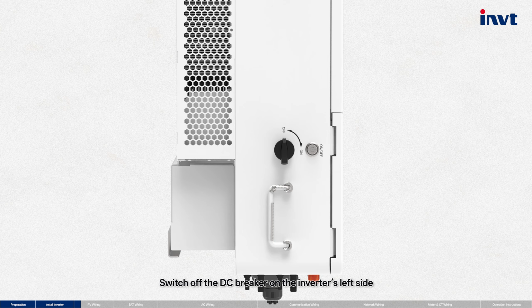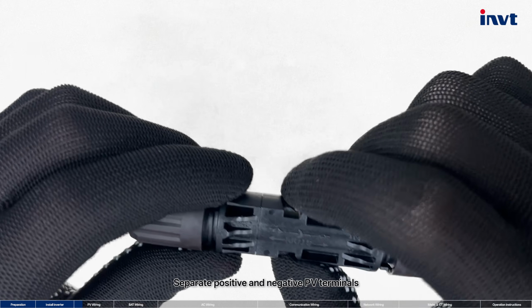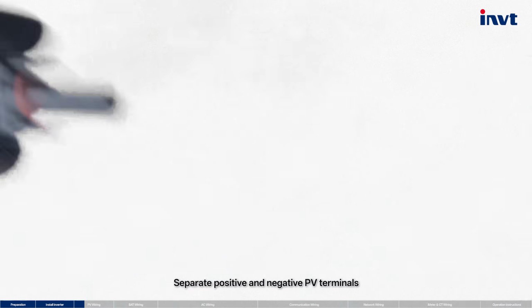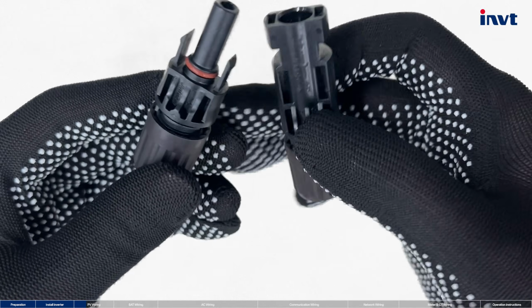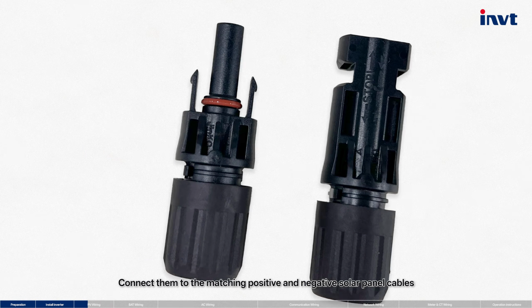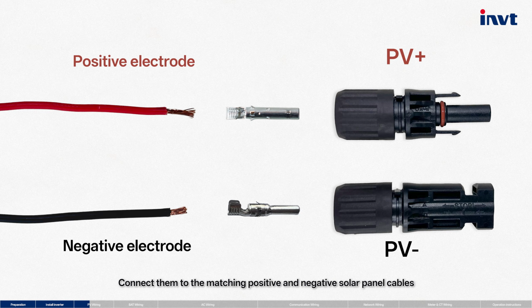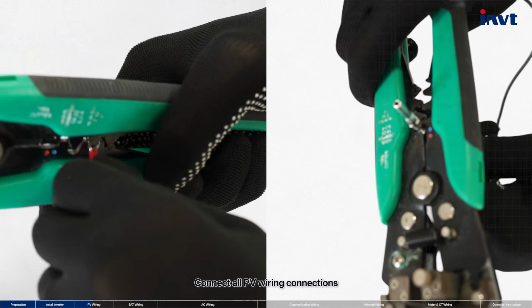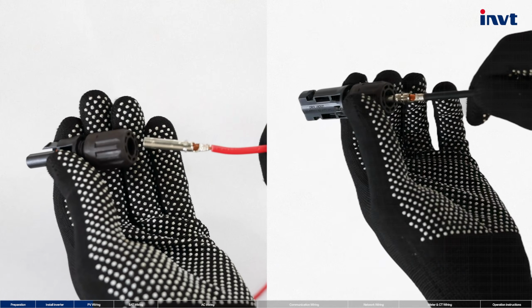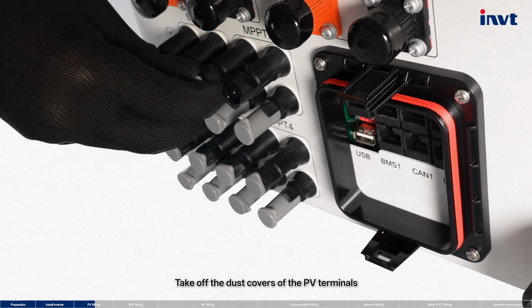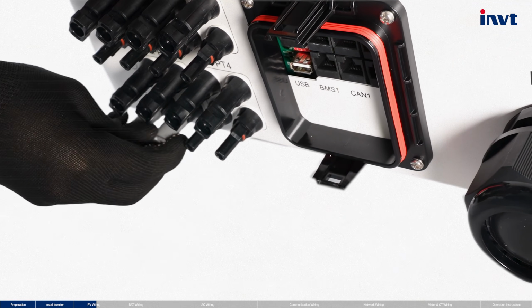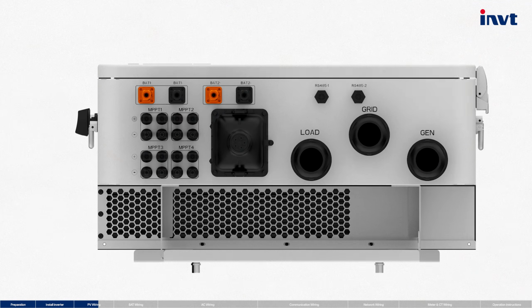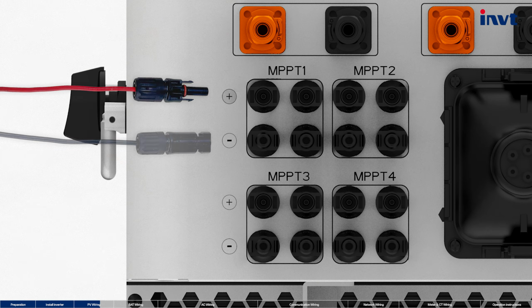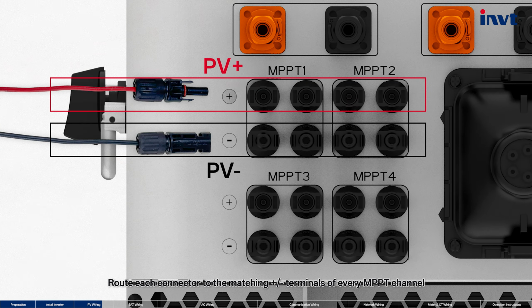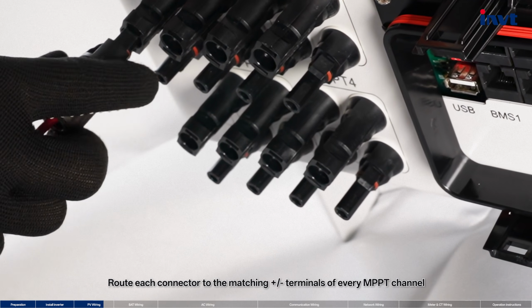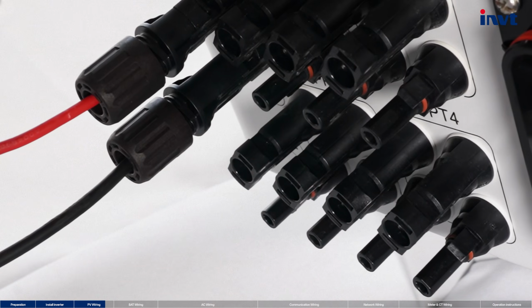Switch off the DC breaker on the inverter's left side. Separate positive and negative PV terminals. Connect them to the matching positive and negative solar panel cables. Connect all PV wiring connections. Take off the dust covers of the PV terminals. Route each connector to the matching positive and negative terminals of every MPPT channel.